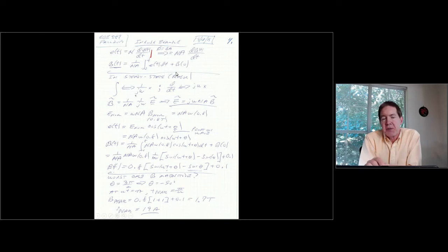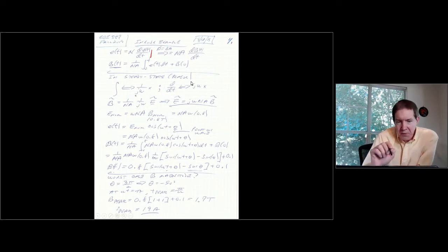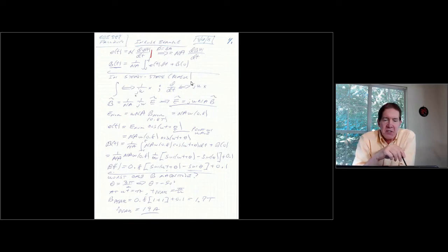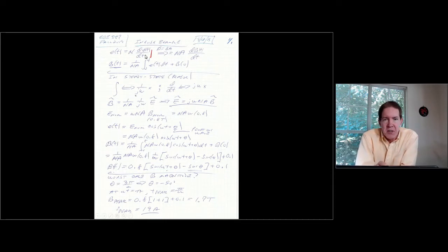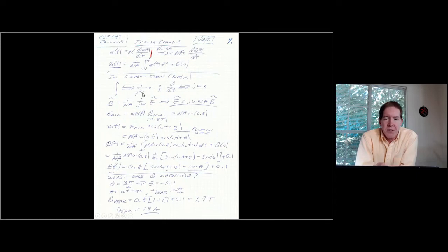The integral relationship between voltage and B is: B = (1/NA)·∫E dt + initial residual flux density. Now, I need a way of relating the 0.8 Tesla nominal value to the normal voltage. Instead of writing these relationships in the time domain, I can write them in the phasor domain for steady state. An integral in the time domain corresponds to multiplying by 1/jω in steady state using phasors.